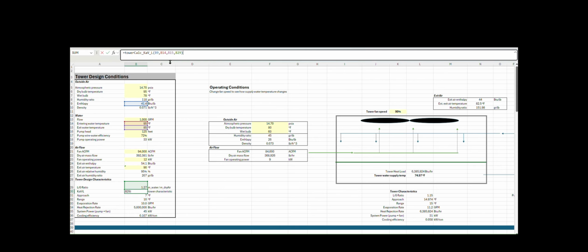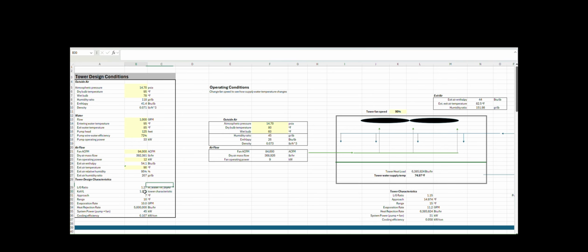we're doing it much more granular in the background, where instead of the 20 steps that I do for DT, I'm doing, I think, 500 or so steps. So it's much more granular in the background. And I get a characteristic value of 1.208. Doing it this way gives me 1.202. So we're pretty darn close by doing it this way. The macro that does it in the background is obviously more accurate, but for our purposes, that's exactly how you can calculate the tower characteristic number.